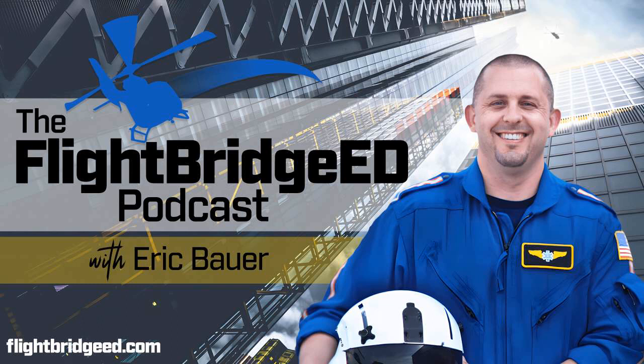All right, so let's recap a few things. I want to go back to this pressure. Always set your maximum delivered pressure limit to 5 centimeters of water below your set pressure limit. Remember, our high pressure limit is always going to be 35 to 40, and you're always going to set your delivered pressure limit at 5 below that. So an example of that would be this.